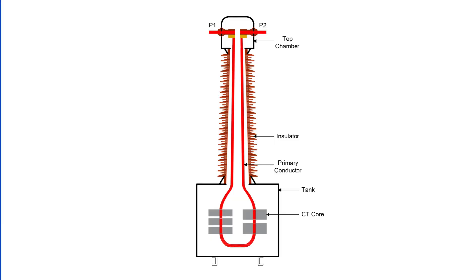Let's not forget what makes dead tank CTs so dangerous today. It's their design drawback. The longer internal conductor path, housed inside a grounded tank, introduces multiple points where insulation can fail. One weak spot, one moisture pocket, one degraded bushing.